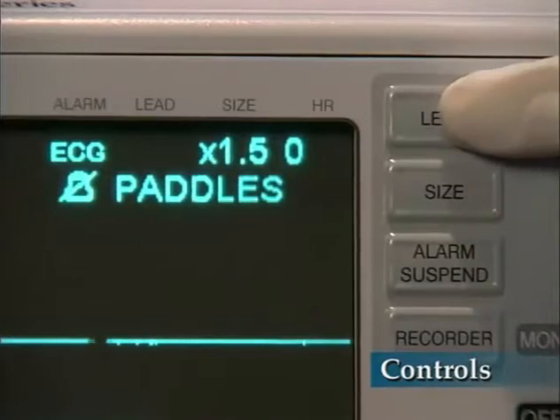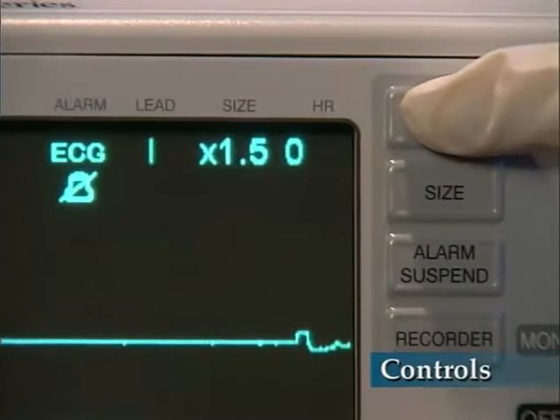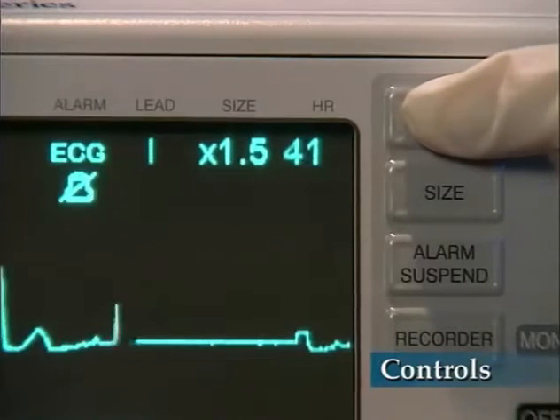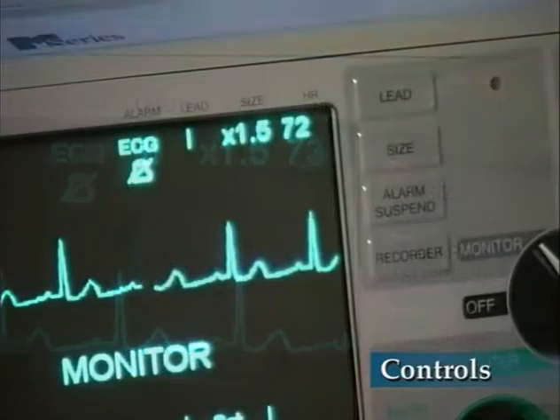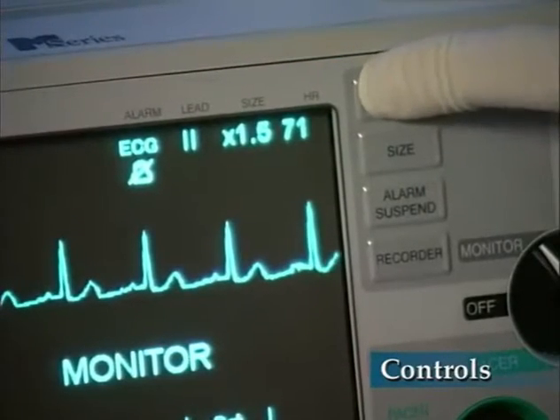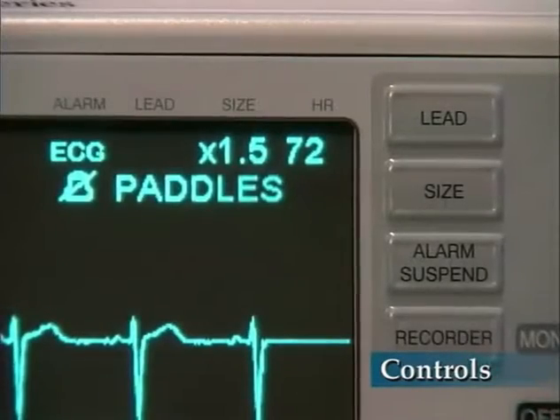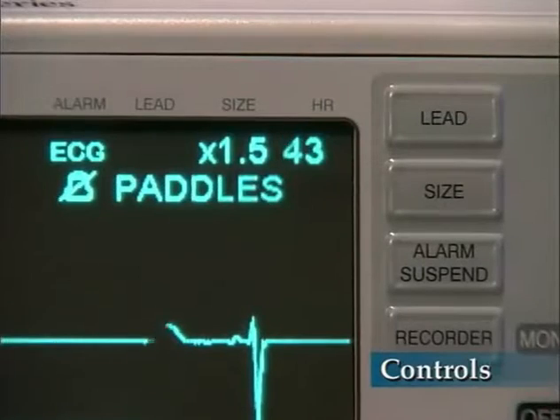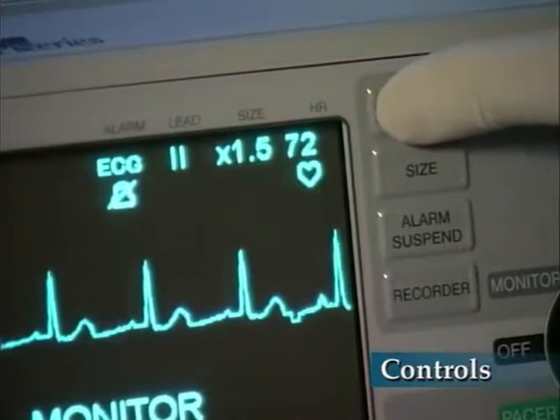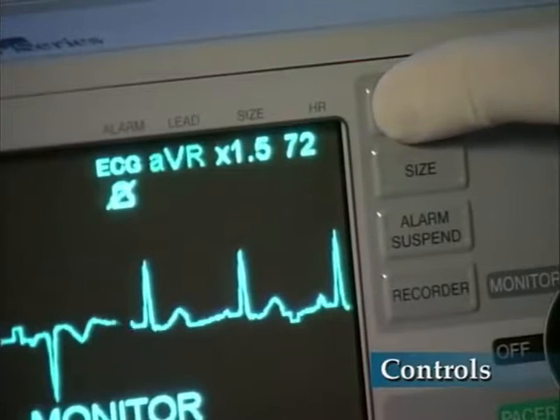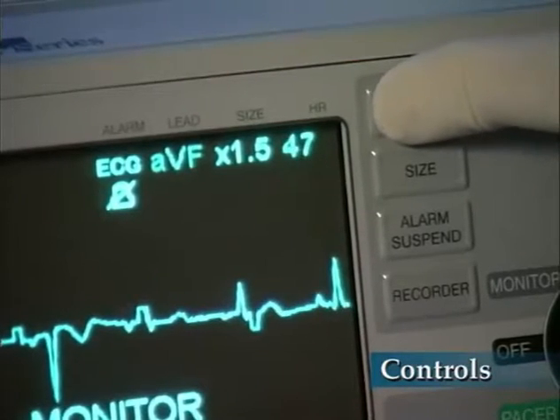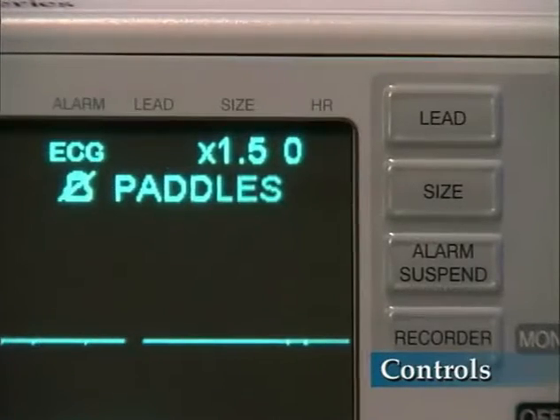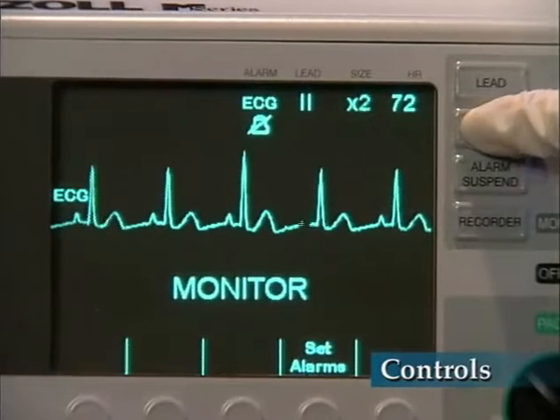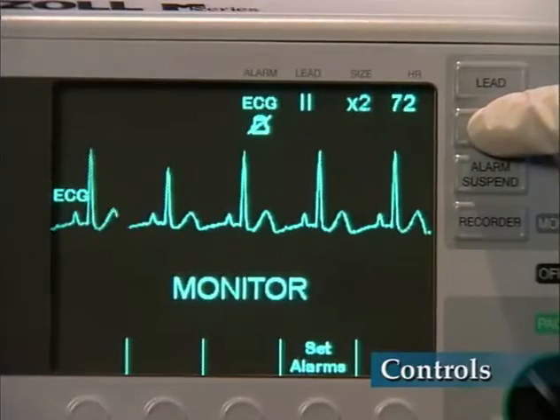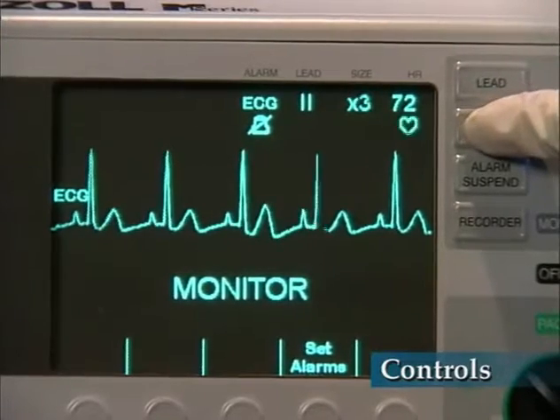Pressing the lead button changes the ECG source and sequentially selects ECG from each of the following lead configurations: 1, 2, 3, and paddles when using a 3-lead cable, and 1, 2, 3, and AVR, AVL, AVF, V, and paddles with a 5-lead cable. The size button allows you to change the ECG size and sensitivity of the signal. Size options are indicated on the display.